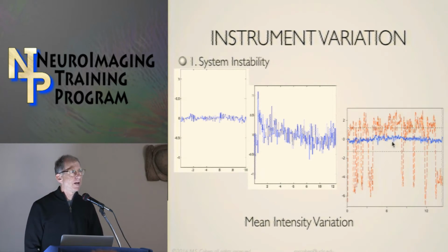There are things that go on to them, and wires break. Gradient coils in particular have a tendency to fray. Lots of things can affect this. The temperature in the room becomes unstable. The coil connections on the RF system are loose. 100 different things.